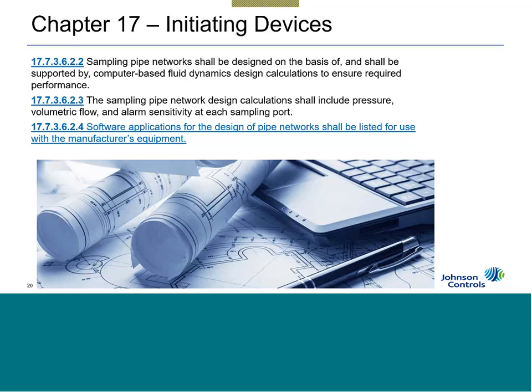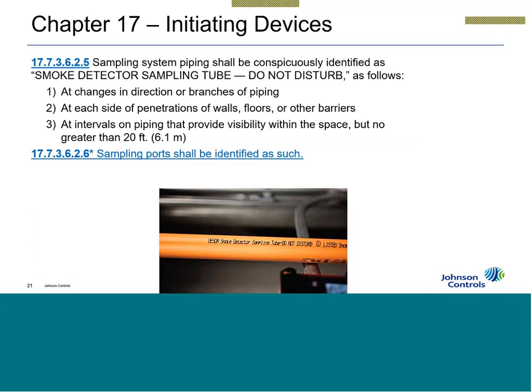So again, trying to give the teeth to the engineers, the AHJs, that when you get a submittal that has a layout for an air aspiration system, you can challenge and say, great, how did you do this? What software did you utilize? And then along with that, the sampling pipes need to be labeled, that the ports are used for inspecting the fire alarm, or for the sampling ports for the Vesda systems or air aspirating systems.